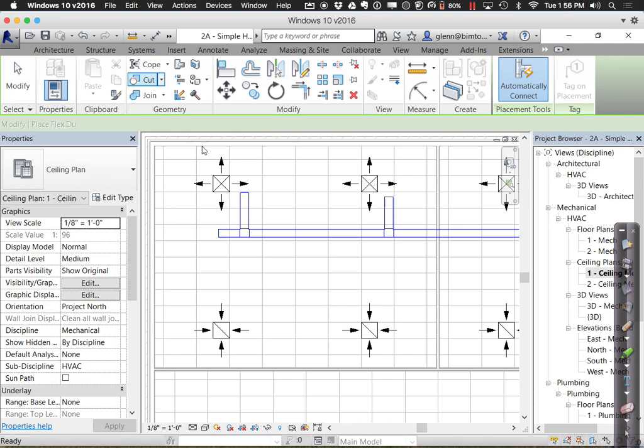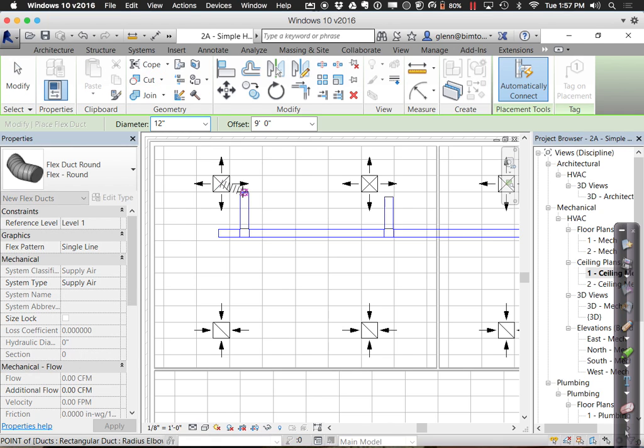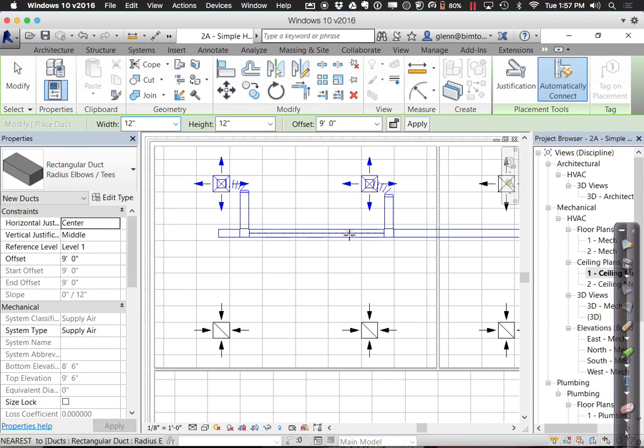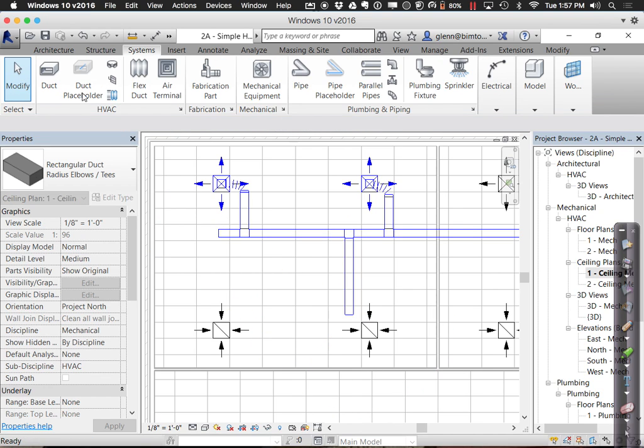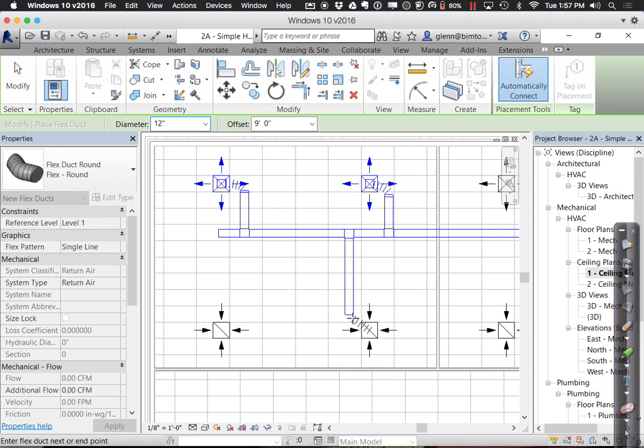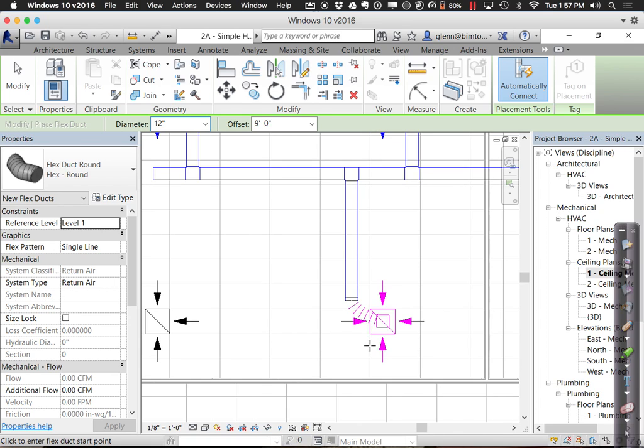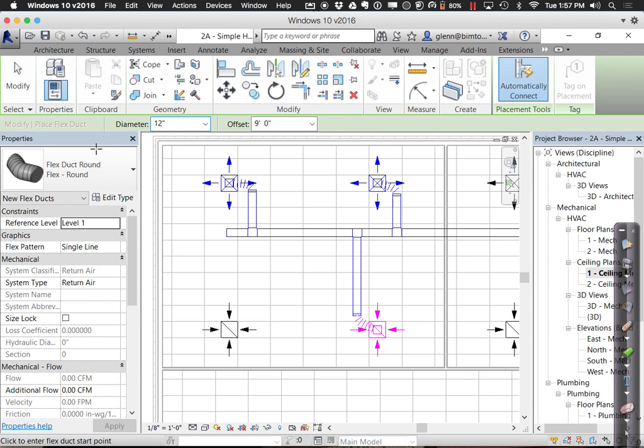For the final little piece, I'll use flex duct to go from the end to the terminal. The reason for that is it gives you a little bit of flexibility spatially, so if it happens to be a few inches off you don't have a manufacturing problem. I'm going to run another duct over here to purposely show you an error. I'm going to try to connect a return into the supply. Notice it gave a color difference — that isn't what we want — so I'm going to take that back out.